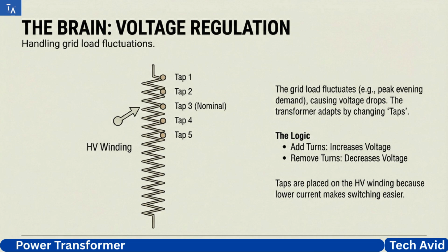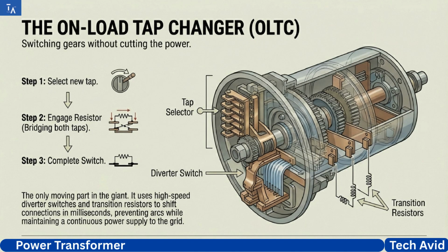The grid isn't static. Demand surges at dinner time, causing voltage to sag. The transformer has a brain to handle this: voltage regulation via tap changing. The logic is beautifully mechanical. To raise output voltage, you add more turns to the winding. To lower it, you remove turns. These taps are on the high voltage side, where the current is lower, making switching easier. And the most advanced ones can do this without cutting power, using an on-load tap changer, a complex switchgear that seamlessly reroutes current mid-flow.